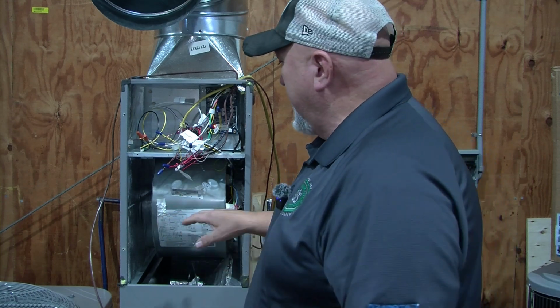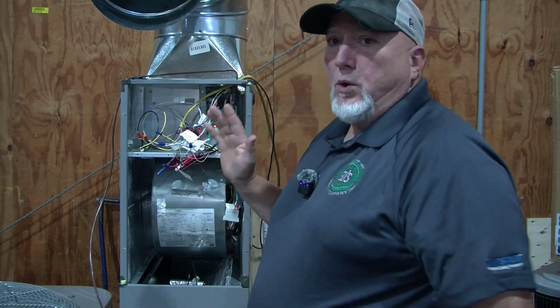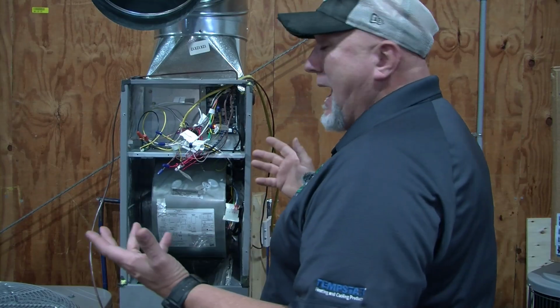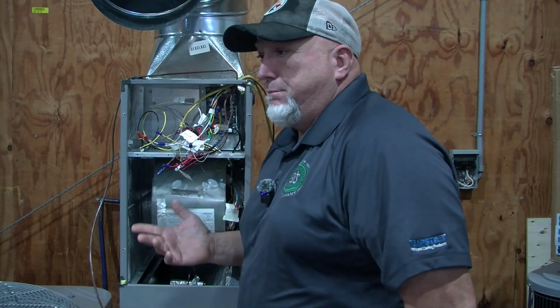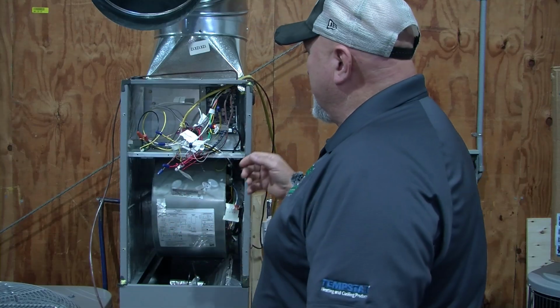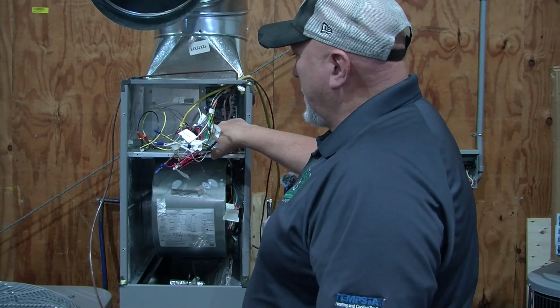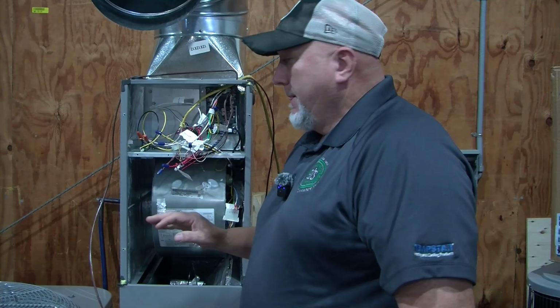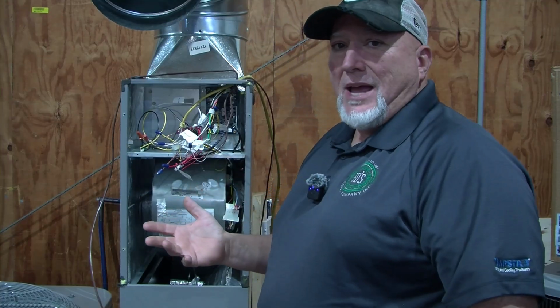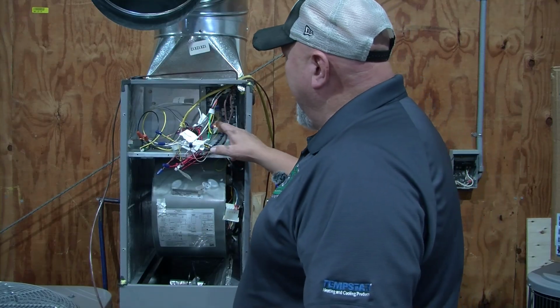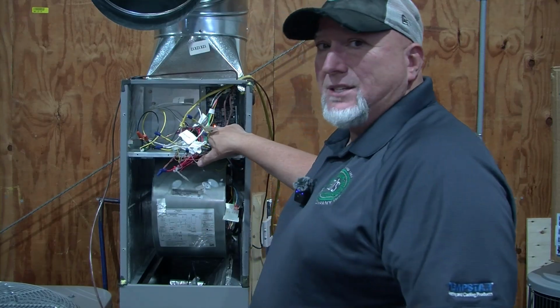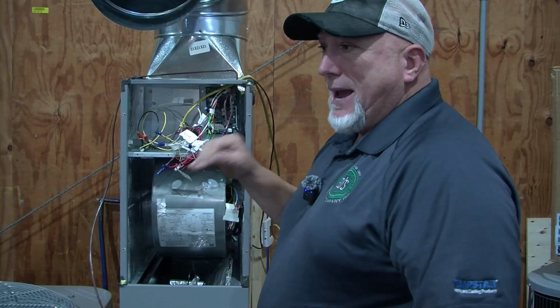The other thing I see is if you have a bad board for whatever reason, maybe you shorted the board out, and that happens too, or maybe it's just a bad board out of the box, that happens as well. You'll see the light not come on and the blower motor stay running. Sometimes that is a sign of a bad board. Then I've seen it where if you go through the test cycle and then it comes back and it's flashing a code, you could have a bad sensor.